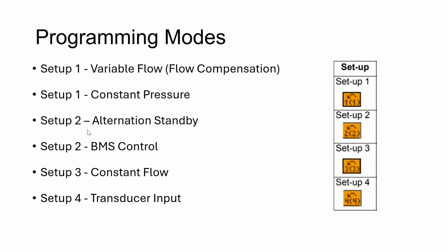Here's a question that was not posed today. It was not on the question list, but it comes up periodically, and I'm going to ask the question and then answer it. The question we get periodically is, where is the pressure sensor? And the answer is, there are no pressure sensors. It's all done with software. And it actually does take a lot of work at the factory. We need to map out all of the information, and so now the drive knows its speed and its current, and because it knows that data, and that's part of the information that helps make the curve, it can stay on those curves. So that's how it does it, and there's programming involved in that regard.